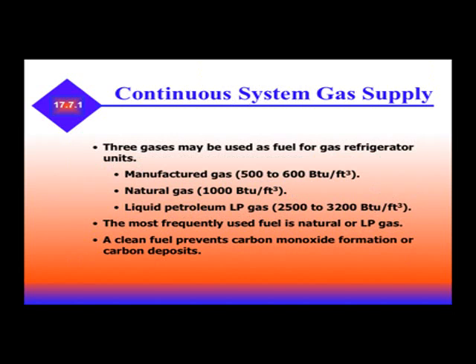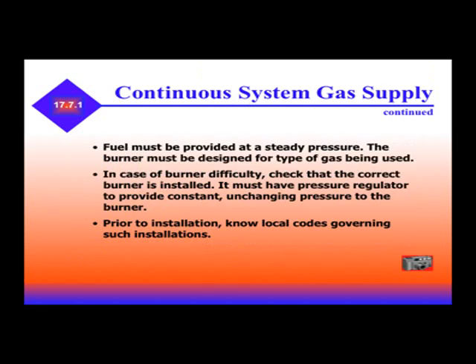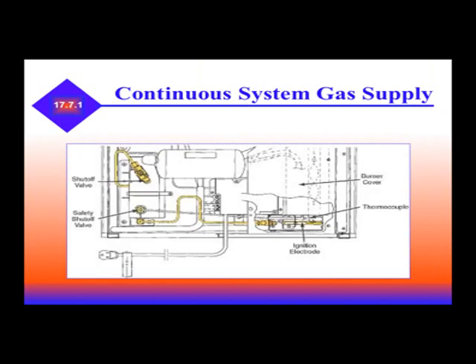Three gases can be used as fuel for gas refrigeration: manufactured gas, natural gas, and liquid LP. The most frequent use is natural gas and liquid LP. A clean fuel prevents carbon monoxide formation or carbon deposits. Fuel must be provided at steady pressure. The burner must be designed for the type of gas being used. In case of burner difficulty, check that the correct burner is installed. It must have a pressure regulator to maintain constant pressure to the burner. Prior to installation, know the local codes governing such installations.